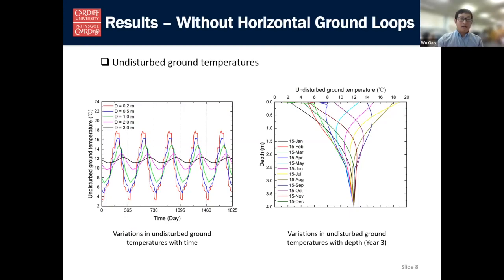In this slide, the results of undisturbed ground temperature, namely before the installation of horizontal ground loops, are shown. On the left, it shows the variation in undisturbed ground temperature with time at various depths. As can be seen from the figure, the amplitude of ground temperatures decreased with increase of the depth. Curve peaks will shift with depth. In addition to that, an annual periodic pattern can be observed in the undisturbed ground temperature after about 2 years. On the right, the variations in undisturbed ground temperature with depths at different days are illustrated. As mentioned, ground temperature varies temporally and spatially.